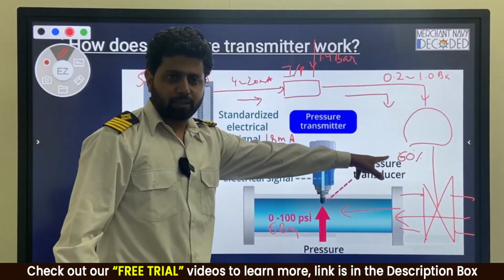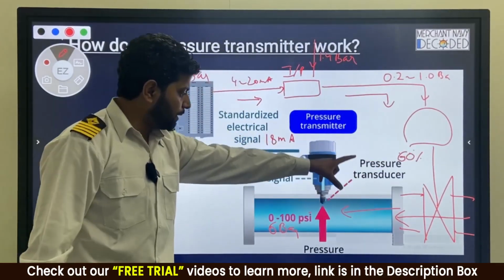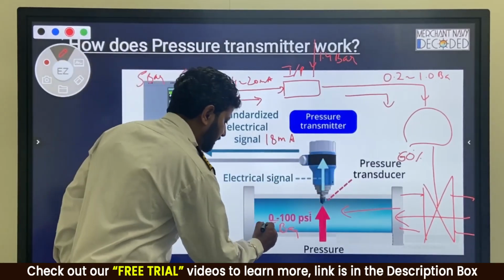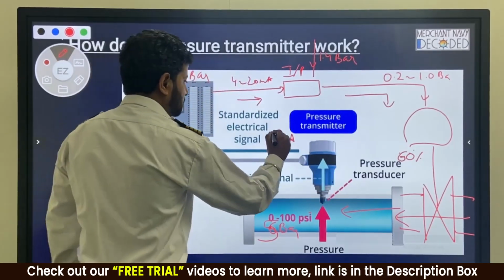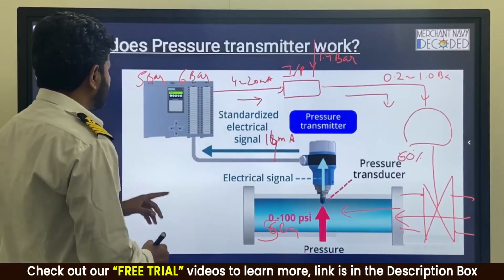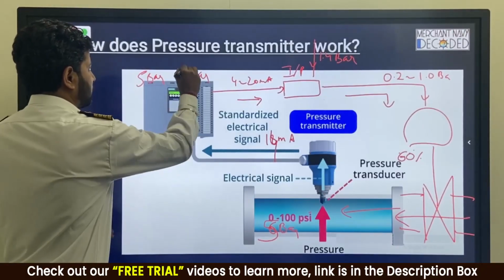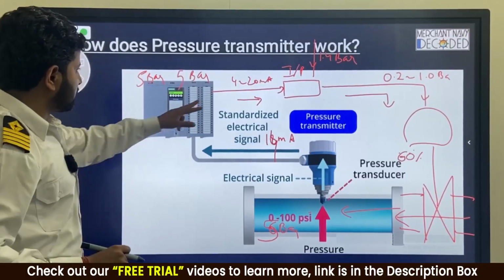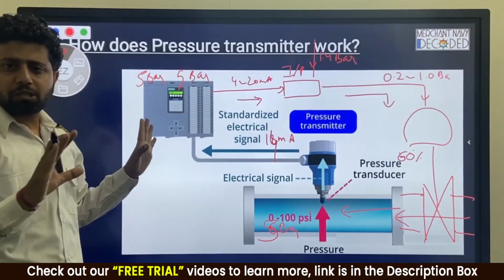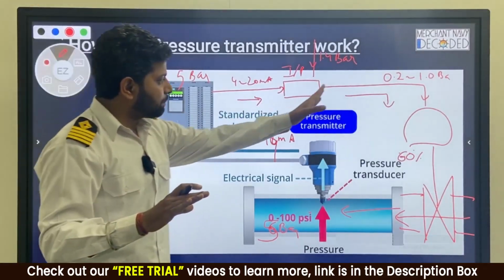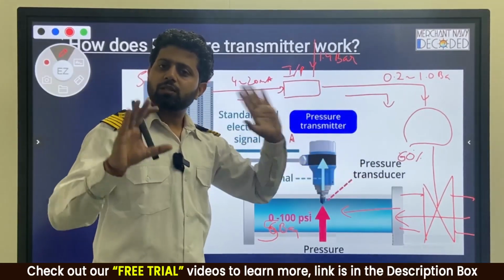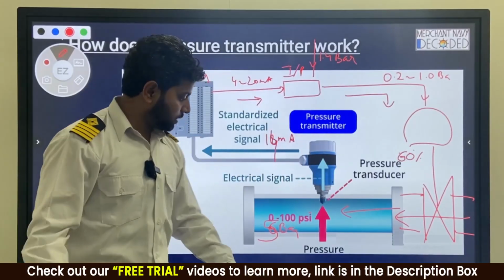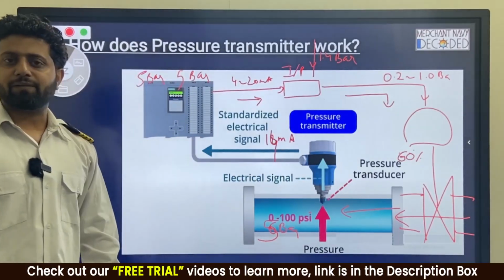The moment I make the pressure valve 60% open, pressure reduces to 5 bar. This becomes 14 milliamps. It says this is also 5 bar. Very good. Current signal goes, no need to change. Let us keep it the same, 60% open. Jai Hind, Jai Bharat, Jai Mata Di, and the pressure is maintained at 5 bar over here.